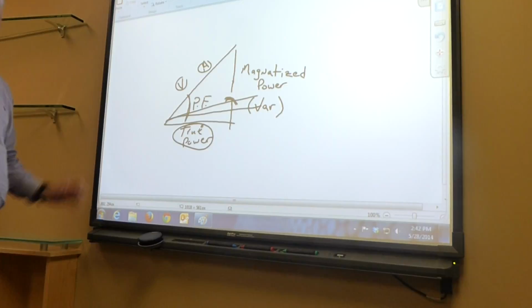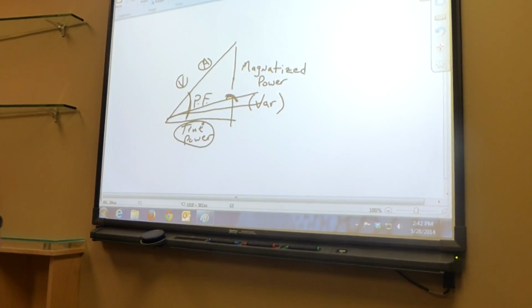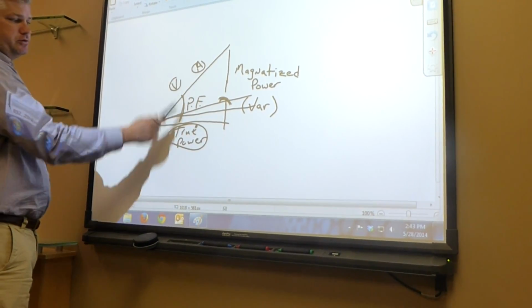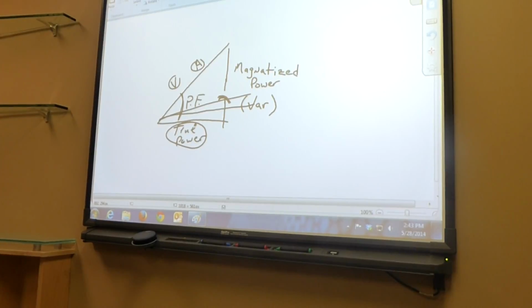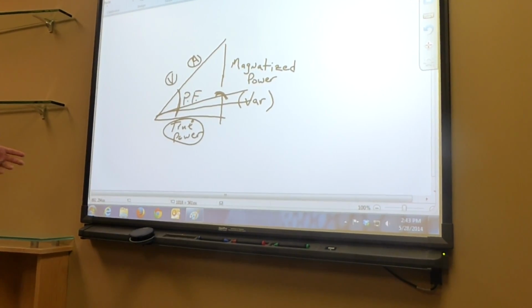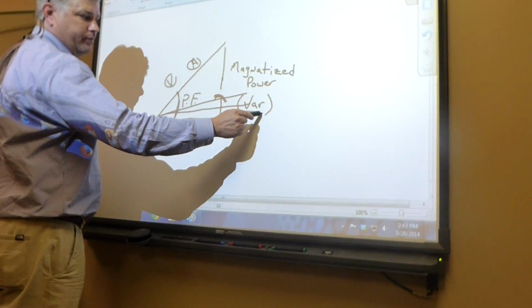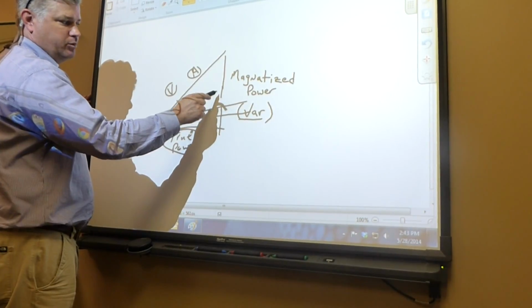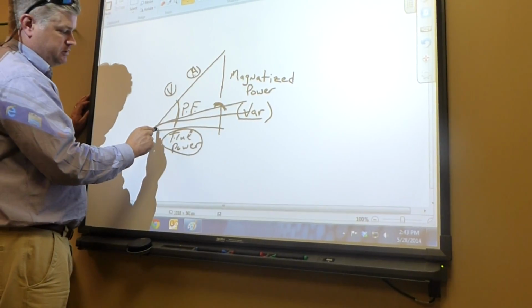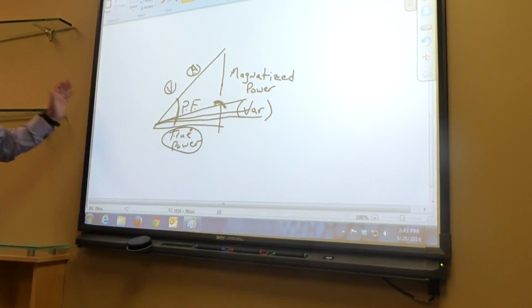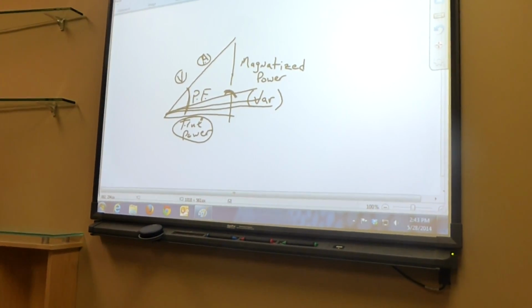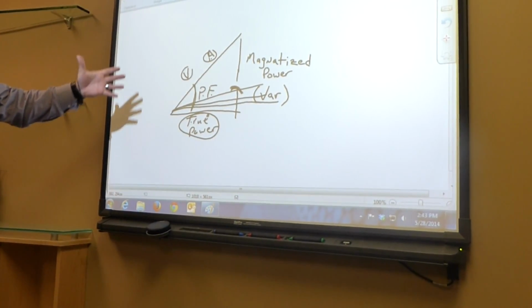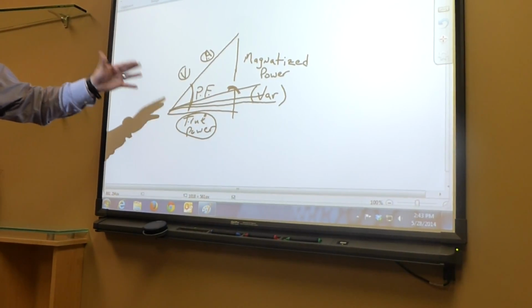these. Well, but that's all contingent upon how accurate your power factor reading is, which is where the metering really comes in. The meter's going to tell us these values over a true 30-day average. Yeah. And we can take that data, plug it into the formula for kVAR, and the formula will equal exactly how much capacitance we need to add based on these values to minimize this angle. So once again, the metering becomes the real critical piece. Yeah, you can't do it unless you have a true picture of what these are, highs and lows and averages.